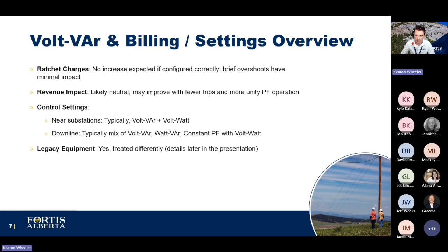Okay. The other question that we get is, will my revenue be impacted? Now, if the site's currently on constant power factor mode, they're absorbing large amounts of reactive power. The revenue is probably going to increase. It may increase in those cases. But again, based on our pilot results, we're not expecting to see it greatly affected. Okay. And the reason for that is because unity power factor is going to happen more often. So you have increased uptime, hence your revenues tend to, if anything, go up. But again, we're talking negligible changes here.